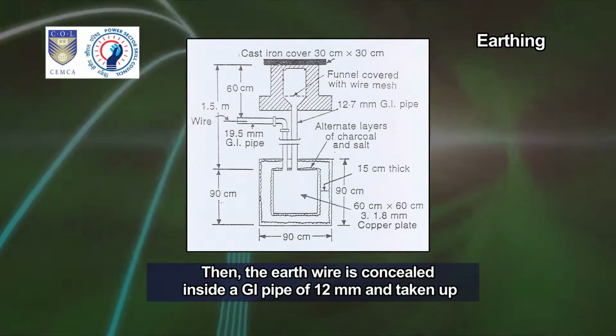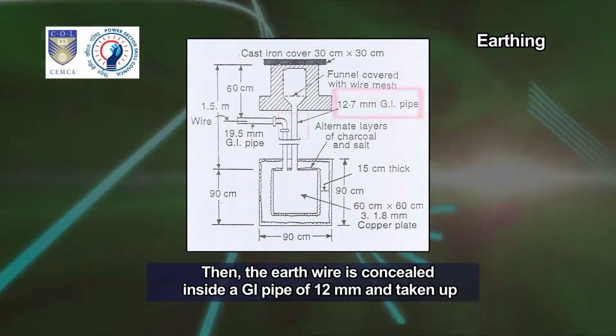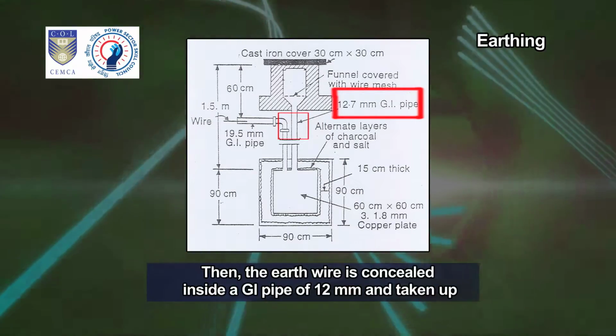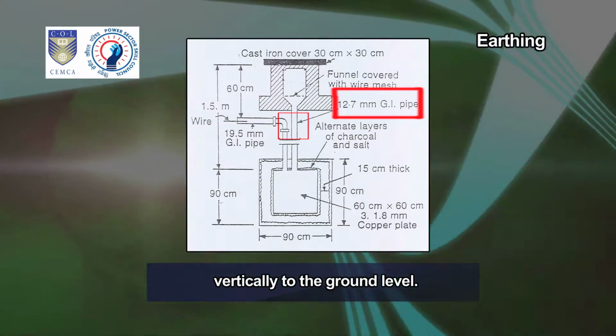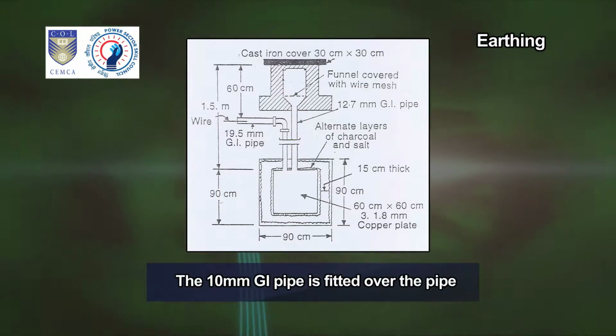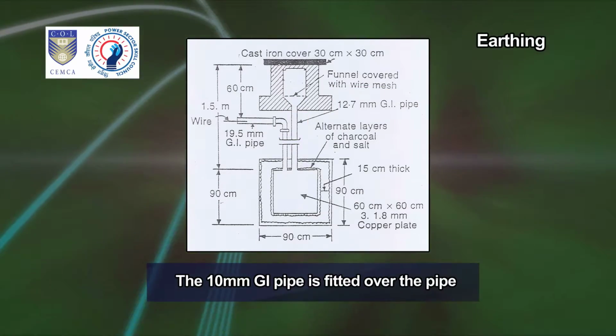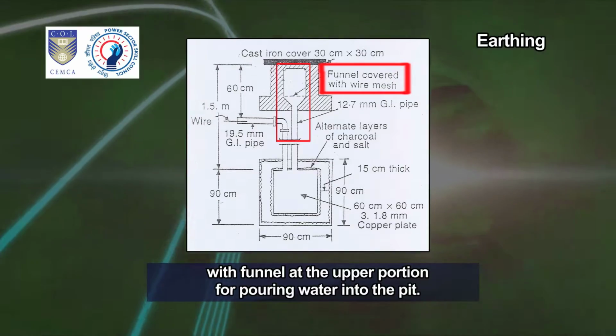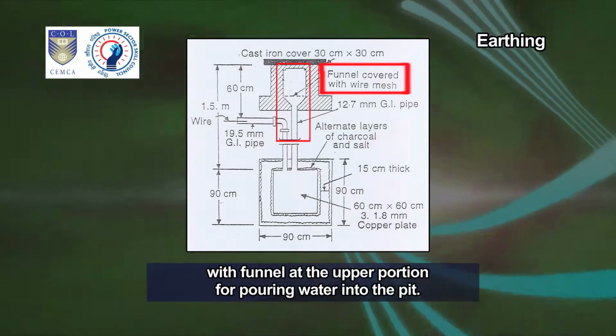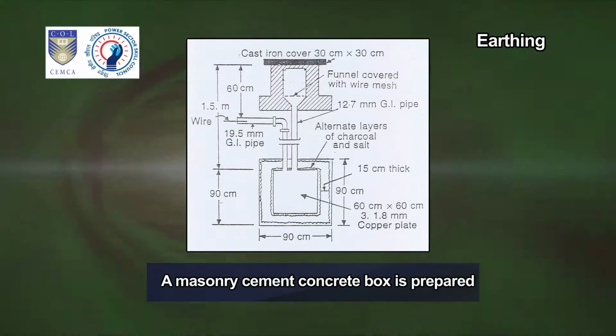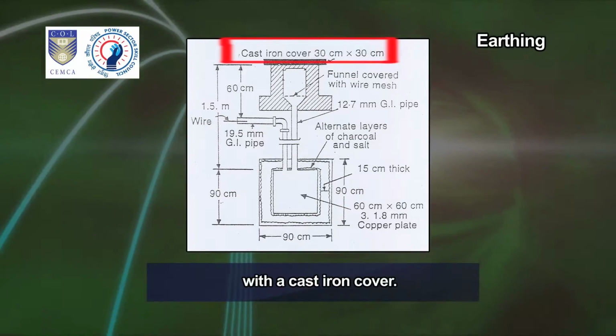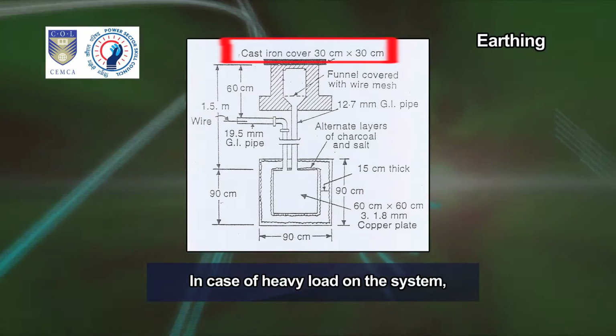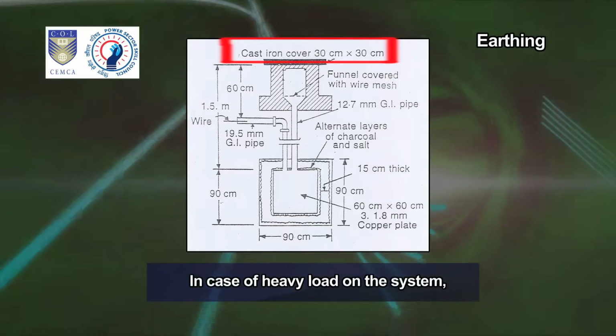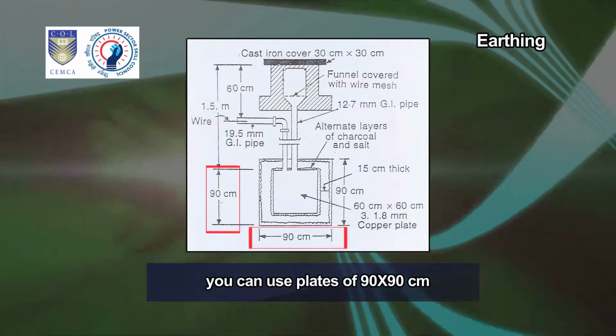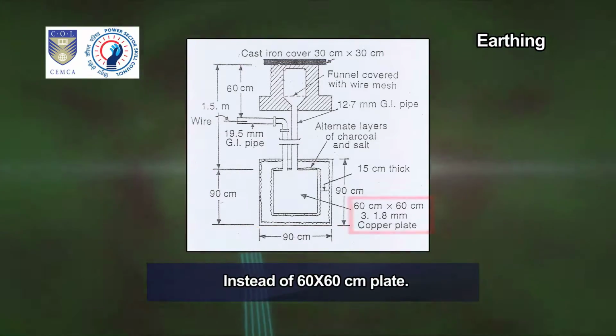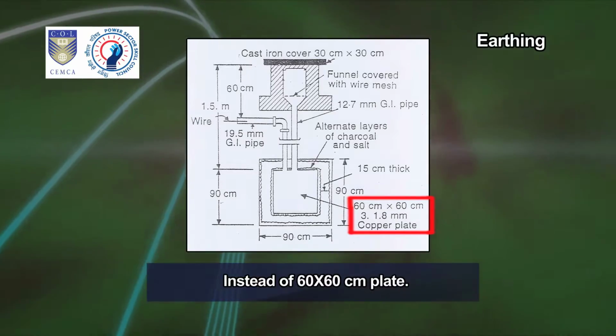Then, the earth wire is concealed inside a GI pipe of 12 millimeters and taken up vertically to the ground level. The 10 mm GI pipe is fitted over the pipe with a funnel at the upper portion for pouring water into the pit. A masonry cement concrete box is prepared with a cast iron cover in case of heavy load on the system. You can use plates of 90 by 90 centimeters instead of 60 by 60 centimeter plates.